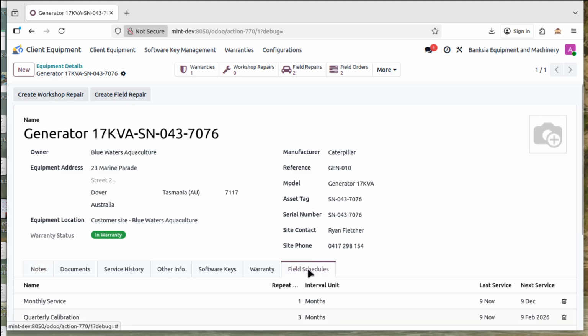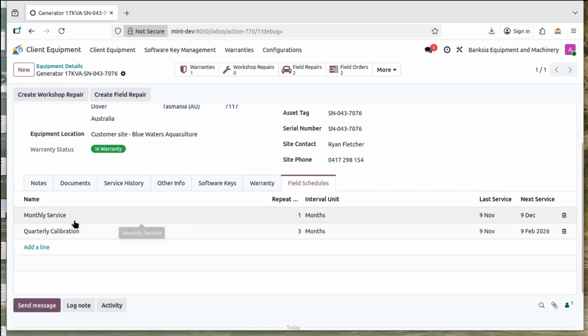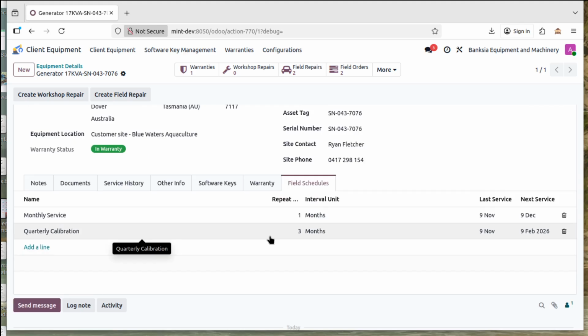Our schedule means we can automatically create these jobs on a frequency determined by however you need to manage it. Some pieces of equipment require monthly calibration checks and monthly services, some require weekly services and quarterly calibration checks. Could be any variety of things. But these regular scheduled activities will be created automatically.